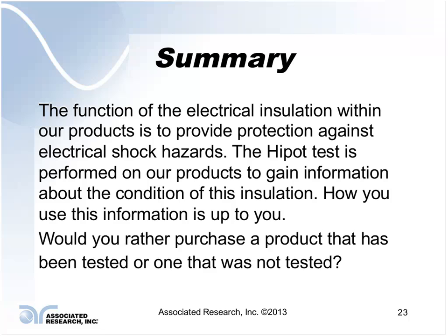Where you run into questions and problems is where insulation has degraded due to age, and if you Hipot that insulation, it may fail.